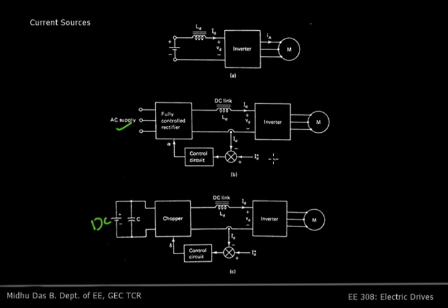The important thing that you have to note here is that, just like a 6-step voltage source inverter, the frequency of the current supplied by the CSI can be controlled by the time period of the gate signals given to the devices. But if you want to vary the magnitude of the current that is flowing, you have to vary ID. As we saw, IS is proportional to ID. So if you want to vary ID, there should be a variable voltage here, and that is how we get a variable current, variable frequency supply from this current source inverter.